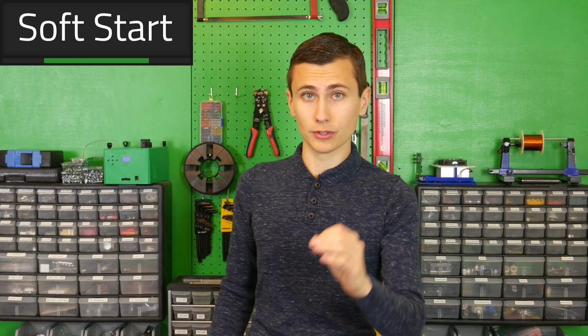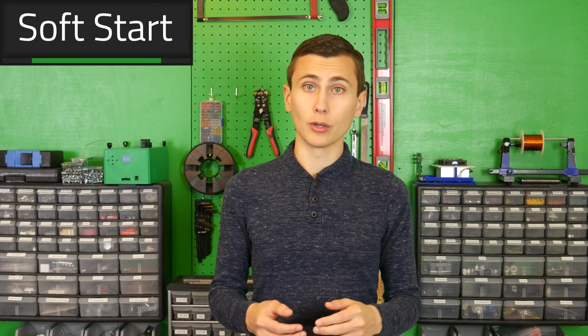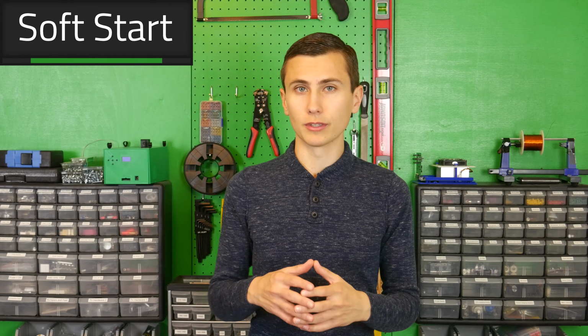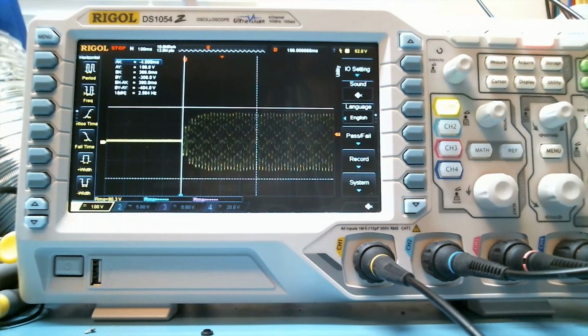The next phase is where this UPS starts to output voltage. Rather than slamming the UPS on with a full amplitude AC pulse, inducing significant inrush current, we take things a little more slowly. Over the course of 4 to 5 half cycles, we provide a progressively increased amplitude on the output. This allows any downstream capacitors to charge a bit more, providing the opportunity for downstream loads to turn on a little more gracefully. Here's what that looks like on the scope.